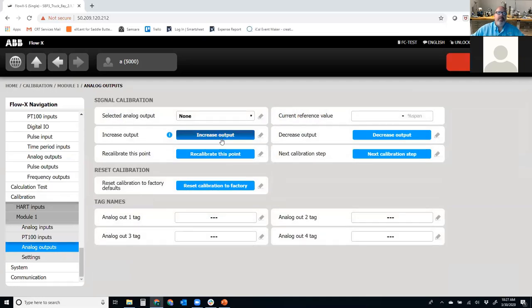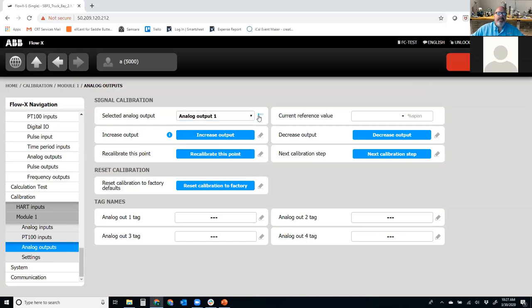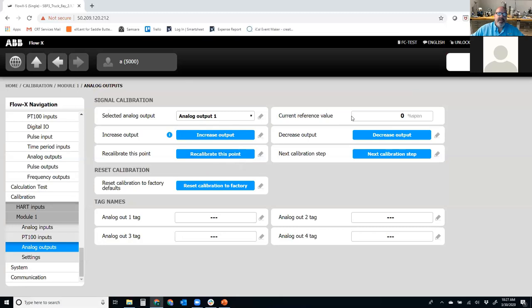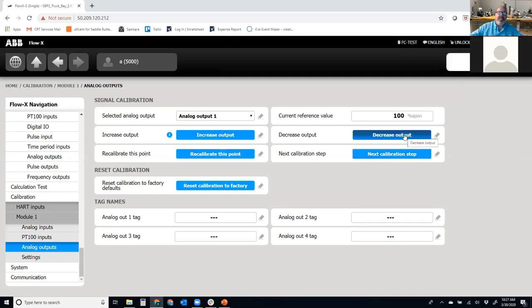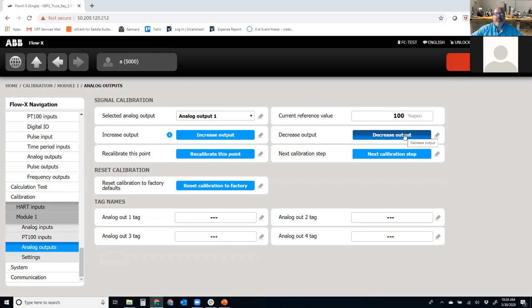If I'm the one who's giving an output, I'll go through and I'll actually increase or decrease my output at zero and then lock that in. I'll go to 50% of the process and a hundred percent of the process and I'll increase or decrease it. What that does is both on the input and the output, it creates a linearized calibration curve to know that there's a slight offset in what the actual voltages we're reading.